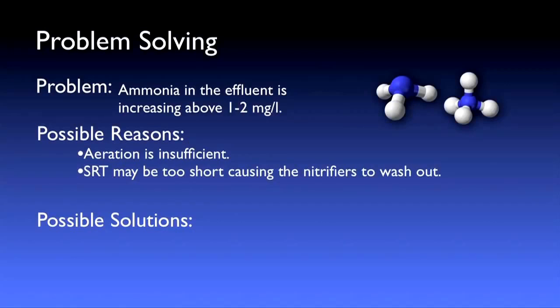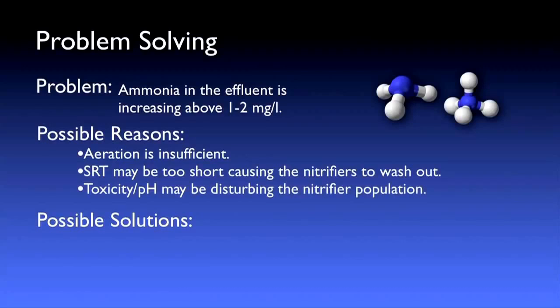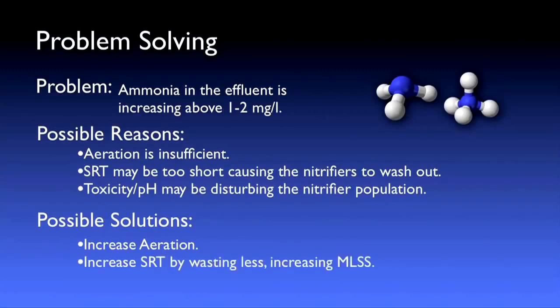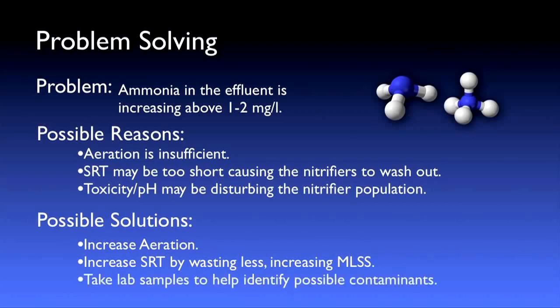Nitrifiers are also very sensitive to changes in pH or toxic conditions, which could also be causing the performance loss. The possible solutions are straightforward: if low DO is the culprit, full nitrification will return by increasing aeration. If temperatures have dropped, the SRT may need to be increased to maintain a healthy nitrifying population. If pH or toxicity is the issue, specific corrective actions will be required depending on the exact cause.